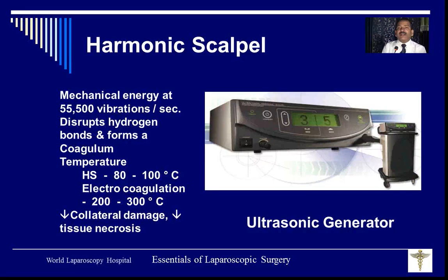Do you know, for harmonic, the terms cutting and coagulation should not be used, because the terms cutting and coagulation are used for electrosurgical machinery. It is called minimum and maximum. If vibration is low, coagulation will be more. If vibration is fast, coagulation will be less and cutting will be fast. Am I clear? But harmonic always cuts with coagulation. It is not like that it will coagulate and it will leave you. It cuts and coagulates together.